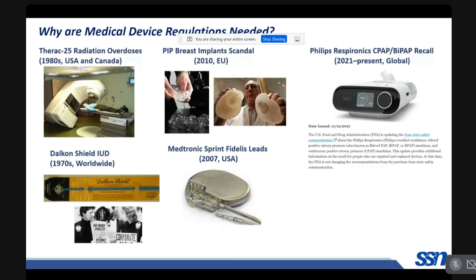Okay, then when it comes to this one, Medtronic Sprint Fidelis leads. Here, this is an implanted defibrillator for the heart. But the leads were prone to breaking, and this could cause the defibrillator to misfire at inappropriate times. Which means that the defibrillator was triggered unnecessarily, and this was not needed at that specific time. Okay, so the leads needed to be recalled, and removing them was risky, and this put the patients at risk.